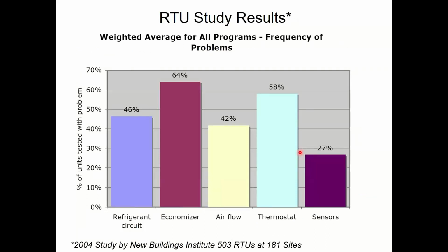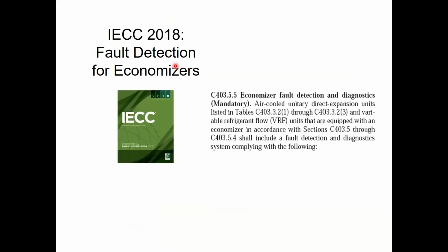You remember this we looked at before, and we said most economizers are a problem? So you're telling me the energy code says put all this economizer stuff in, even though we know it's going to suck and not be set up right or going to be broken. Yeah, that's what it said for years. And then, I don't know, 4 or 5 years ago, I think it was with the 2015 code, we added fault detection and diagnostics. We meaning the code people, not me. They added fault detection and diagnostics. This is the first thing in the code to have FDD as a requirement.